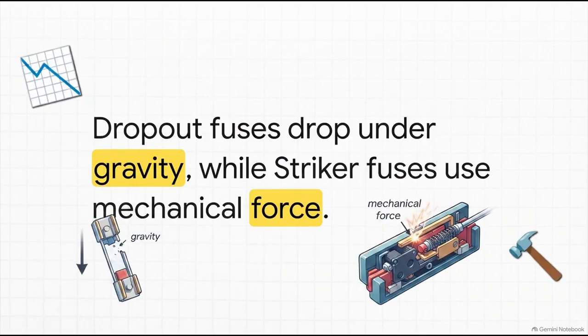Then we get into fuses that do some pretty highly dynamic physical movements. Imagine an outdoor transformer on a pole. That relies on a dropout fuse. When that fuse element melts, gravity literally takes the wheel. It causes the entire fuse to dynamically drop out and swing down from its lower support. It's a huge visual indicator that it blew. Then you have the striker fuse. This one isn't just breaking a circuit, it's practically a little mechanical engine. When it blows, it produces enough mechanical force and physical displacement to actually close indicator or tripping circuits downstream.